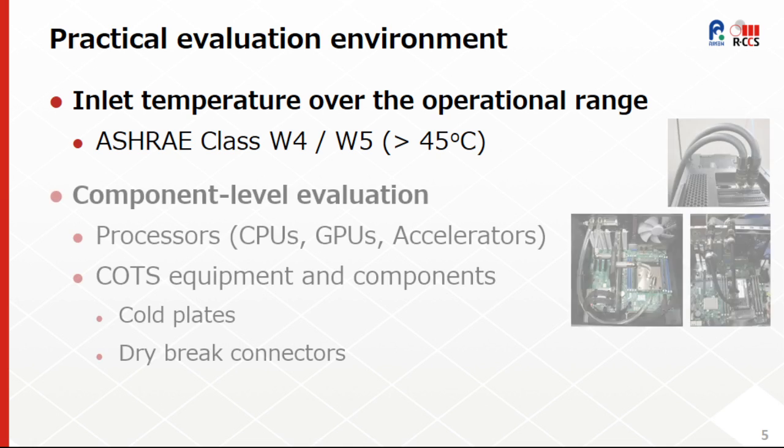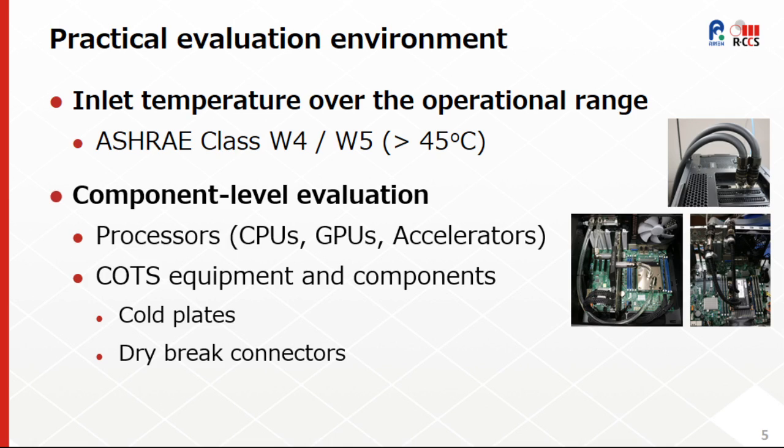To better understand the operational behavior and impact on the system side, we focused on a practical evaluation environment capable of emulating supply water temperature of ASHRAE class W4 and W5. As an initial attempt, we focused on component-level evaluation, mainly processors — that is CPUs, GPUs, and accelerators — also using commodity-off-the-shelf equipment and components, including cold plates and dry break connectors.